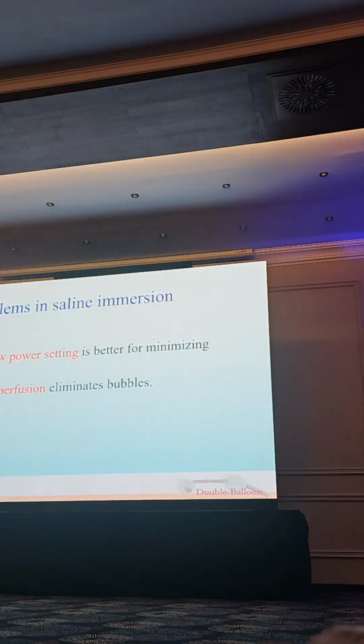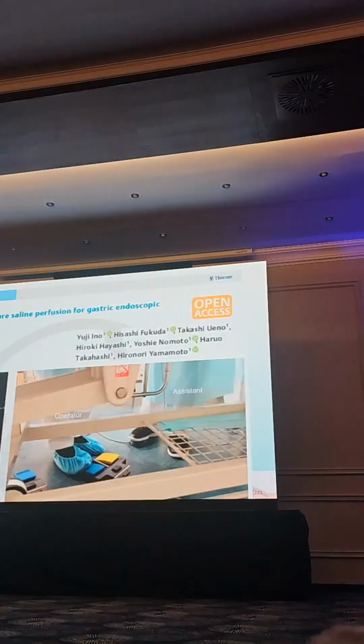So, bubble in saline immersion. What is a bubble? I thought that was the evaporation of water, but if that were just evaporation, after cooling down it should disappear. But this bubble doesn't disappear. So I thought that this is electrolysis. The water is electrolyzed, and by the electrolysis it becomes hydrogen and oxygen. So if that is electrolysis, then using a low voltage setting is better for minimizing bubble formation. That's the reason why I thought that using cutting current, bubble formation will be less, because cutting current has lower voltage than coagulation current. And continuous saline perfusion eliminates bubbles. That's the reason why I studied continuous low pressure saline perfusion for ESD.